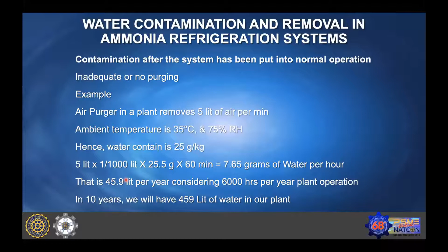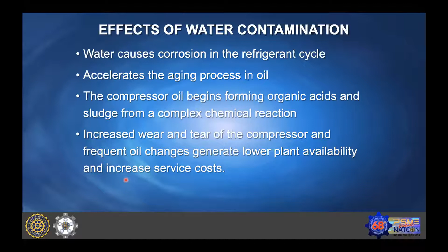So what happens is that when water contacts our pipes, which are mainly steel pipes, it starts corrosion of these pressure vessels or the pipes used in the system. And when water mixes with the oil, it starts the aging process of oil. Oil life gets down. Compressor oil starts forming organic acids and sludge gets formed. It also increases the wear and tear of the compressor. Failures of compressor parts occur, the quantity of oil required increases, and the frequency of oil change increases.